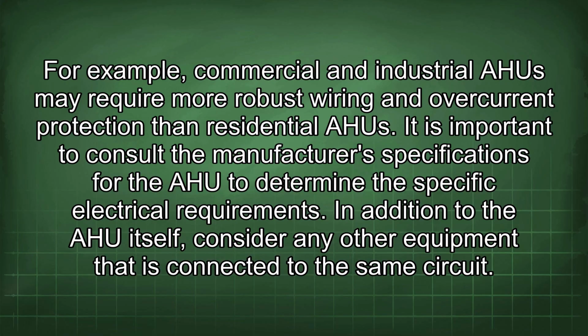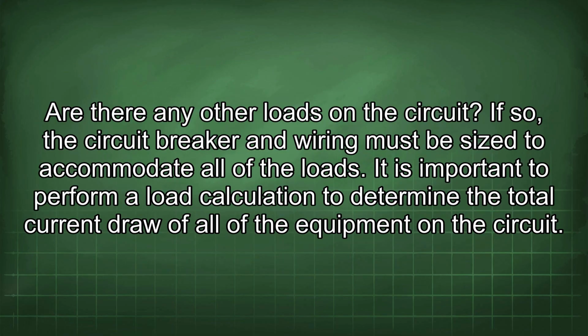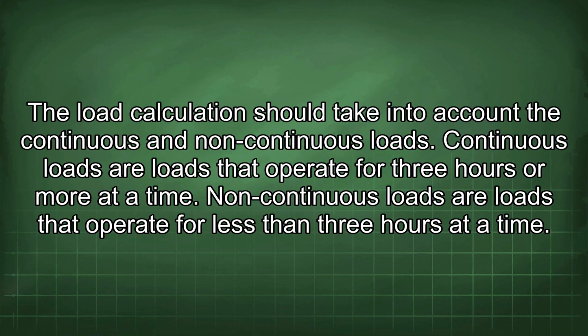In addition to the AHU itself, consider any other equipment that is connected to the same circuit. Are there any other loads on the circuit? If so, the circuit breaker and wiring must be sized to accommodate all of the loads. It is important to perform a load calculation to determine the total current draw of all of the equipment on the circuit. The load calculation should take into account the continuous and non-continuous loads.